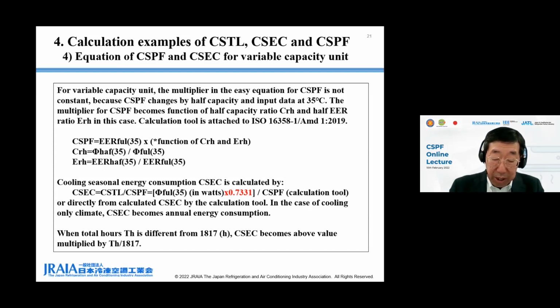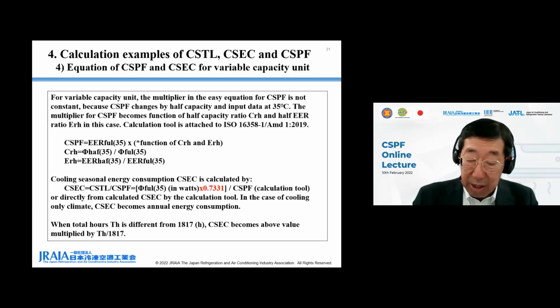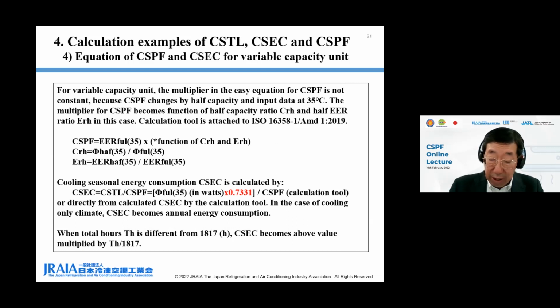In calculation of the cross temperature TC, half capacity ratio CRH is required. Half EER ratio ERH is also required to calculate actual EER at each TJ for both capacity changing zone and on-off zone. The calculation tool is attached to ISO standard 16358-1, Amendment 1, 2019. Cooling seasonal energy consumption, CSEC, can be calculated from CSTL by the easy equation shown here, divided by the result of the calculation tool, or can be calculated directly by the calculation tool.